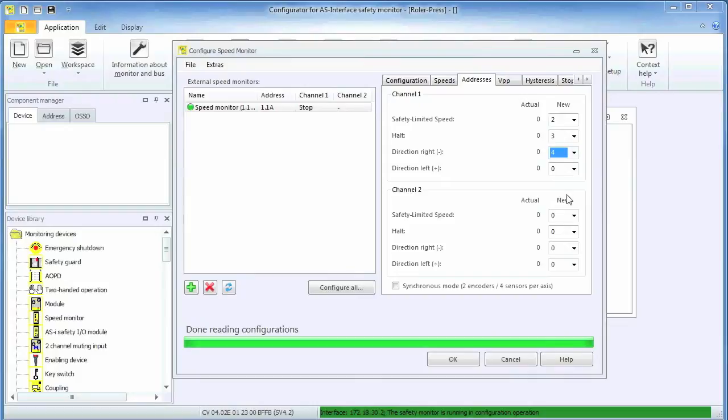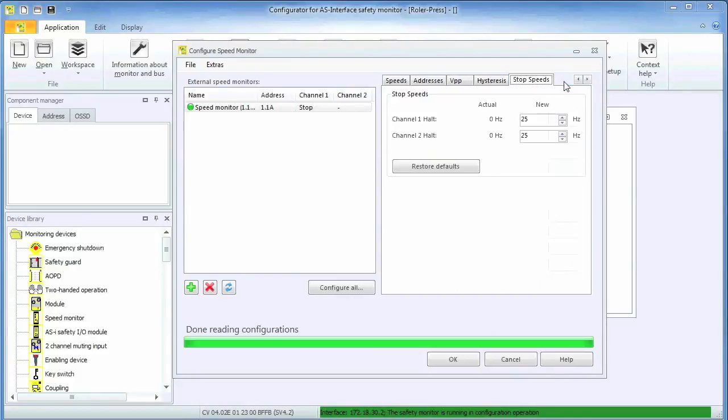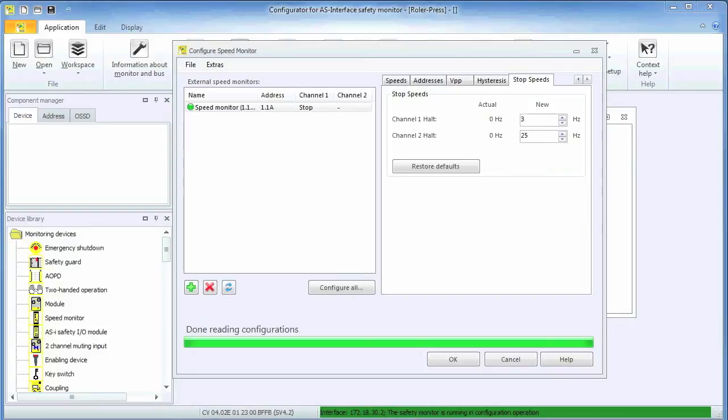The stop tab allows us to set the output frequency of the encoder when it has stopped moving. This number needs to be at least 2 Hz. Lower numbers make no sense from an application point of view either, as even the smallest vibrations would cause the signal to indicate that the rolls are moving. Plus, the lower the frequency, the longer it takes to safely detect motion at all. Consequently, many applications will utilize gearing such that even low rates of rotation result in an appreciable output frequency of the encoder.